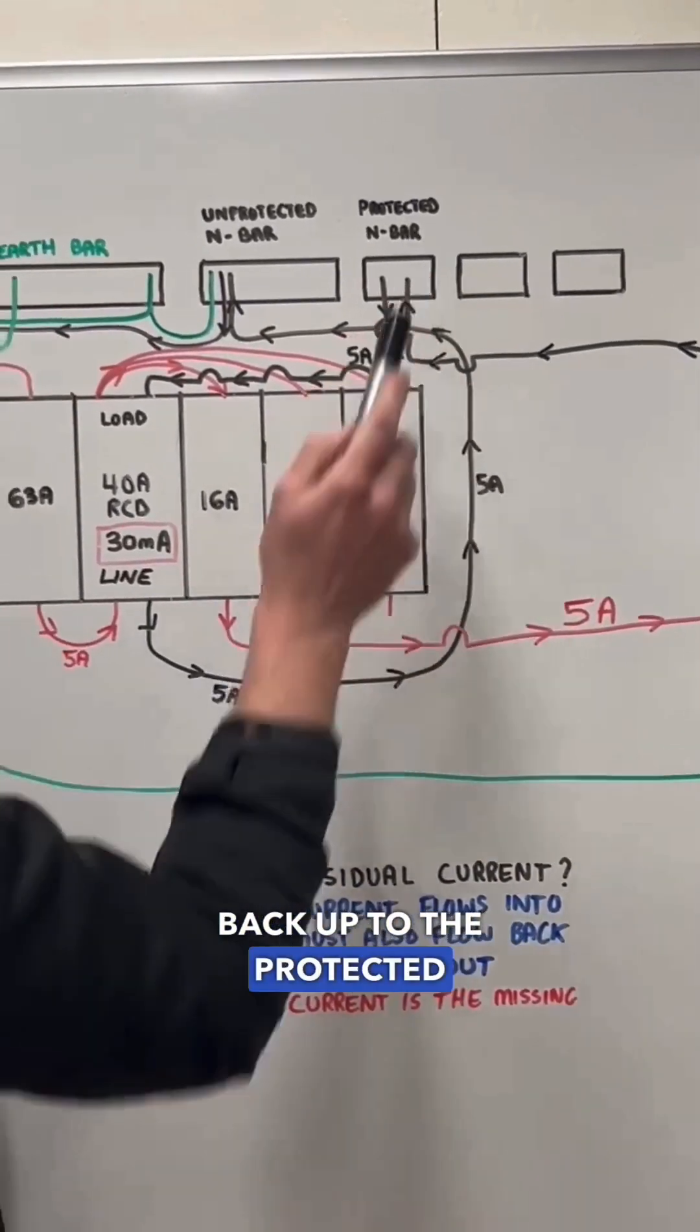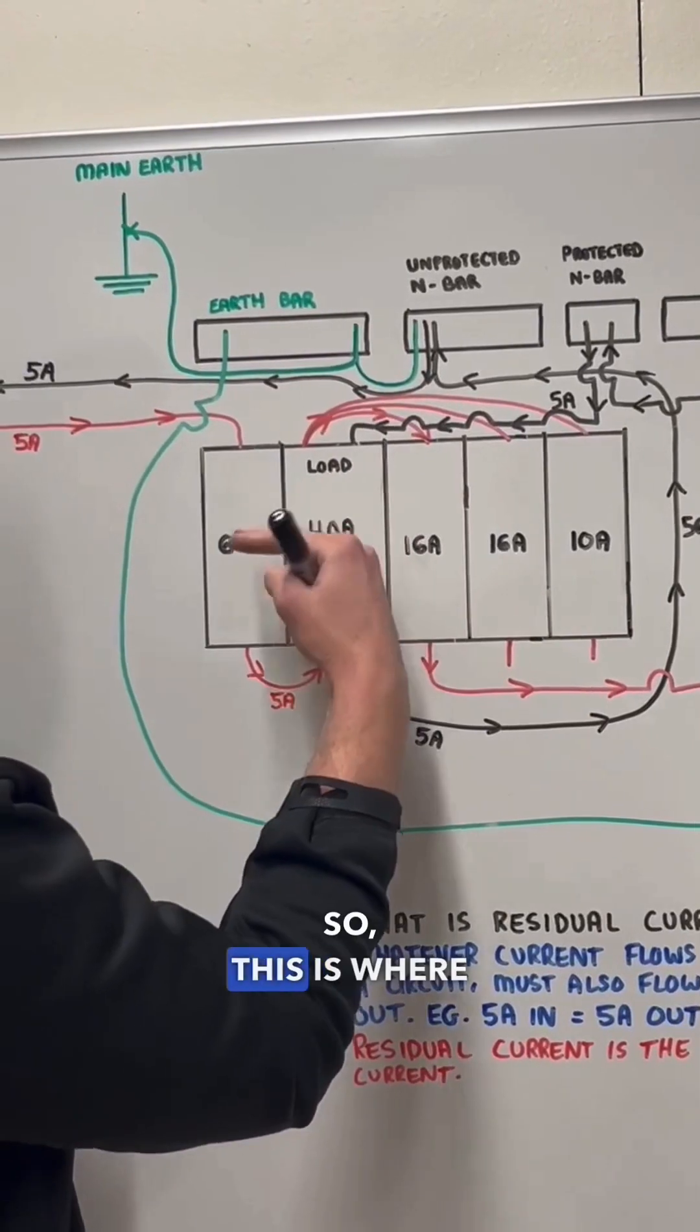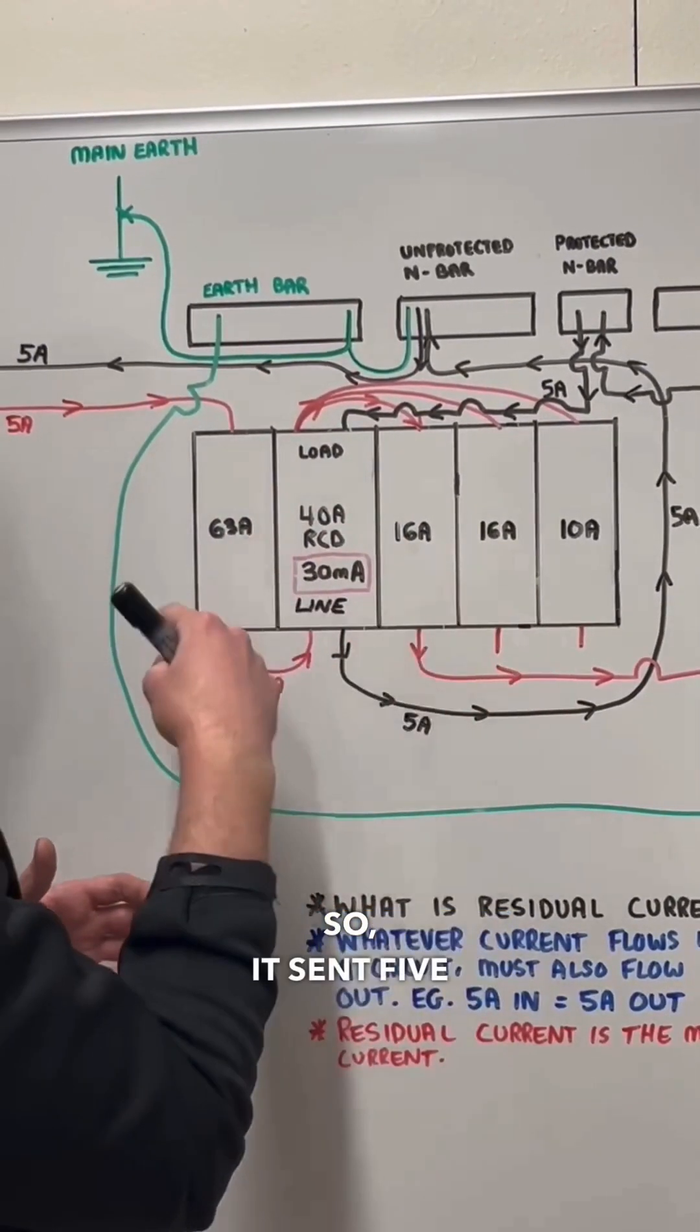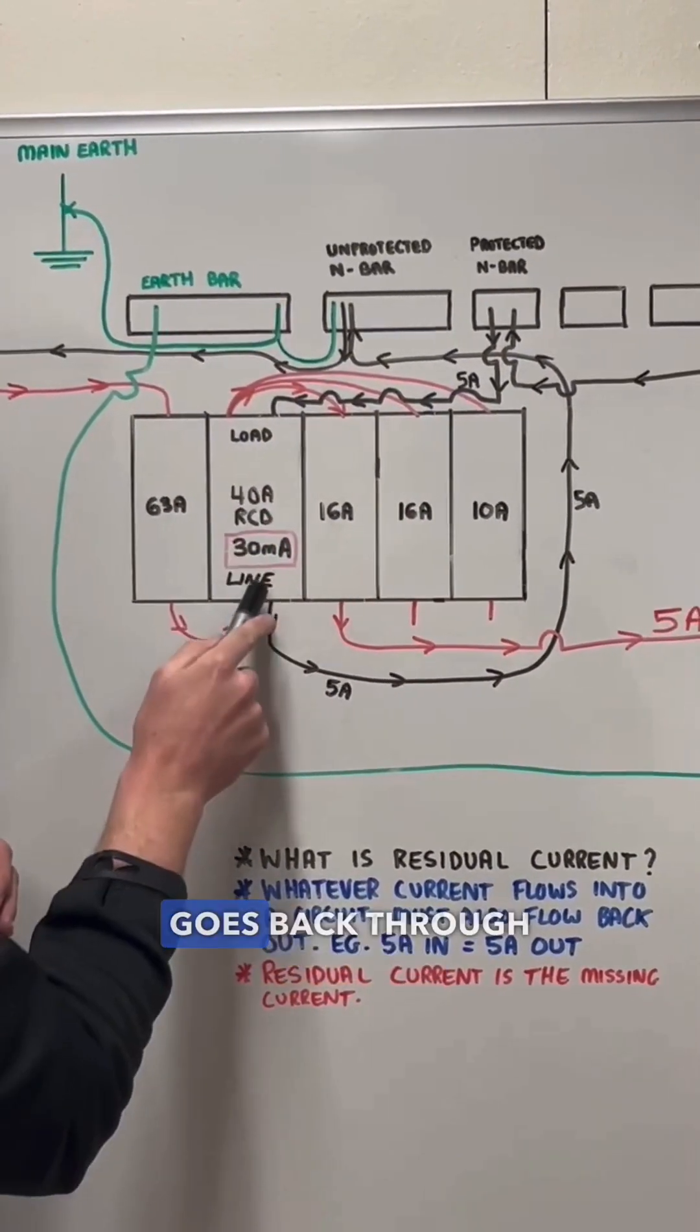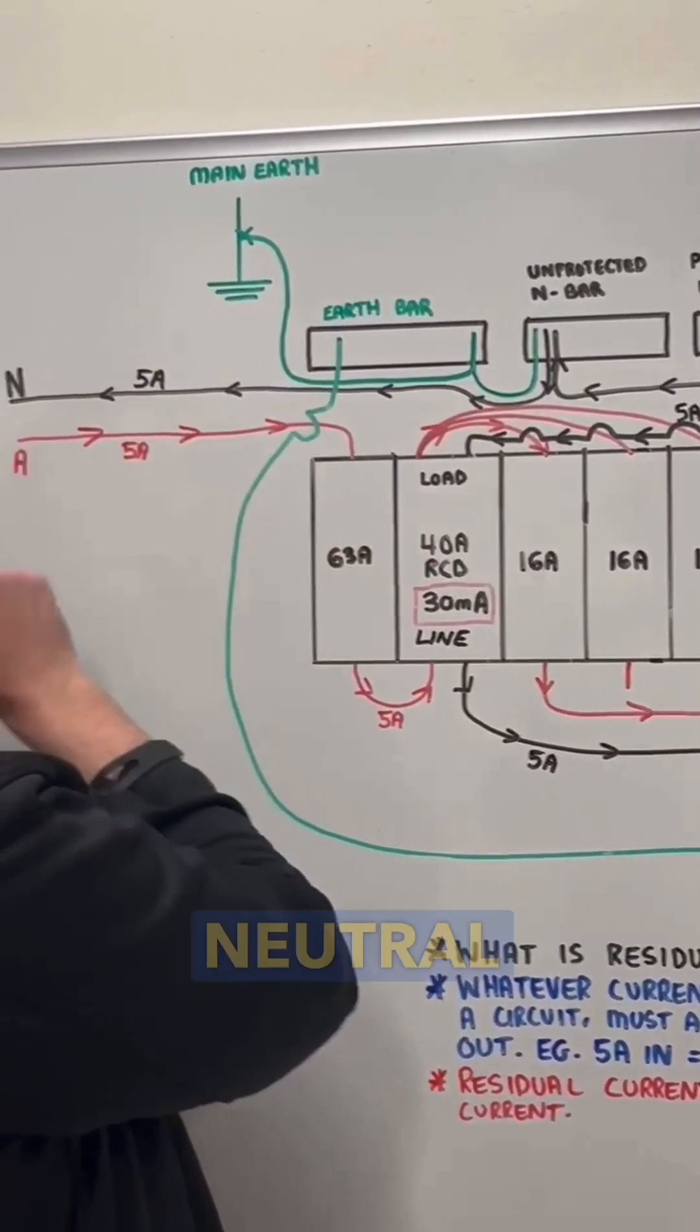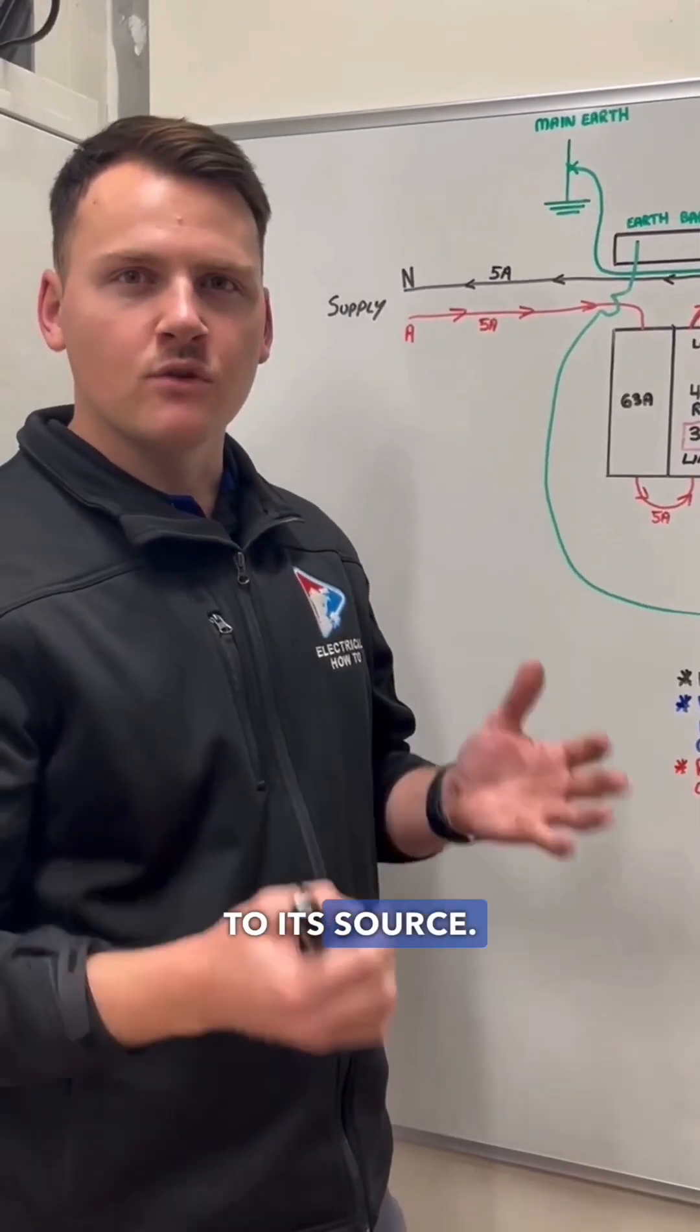Back up to the protected neutral bar and then back to the load side of the RCD. So this is where the RCDs are actually looking for an imbalancing current. It's sent 5 amps out and it's got 5 amps coming back in so it's happy, it's not going to trip off. That 5 amps goes back through the line side, back up to your unprotected neutral bar and then back through your main neutral, back to supply. You've just got to remember current's always trying to get back to its source.